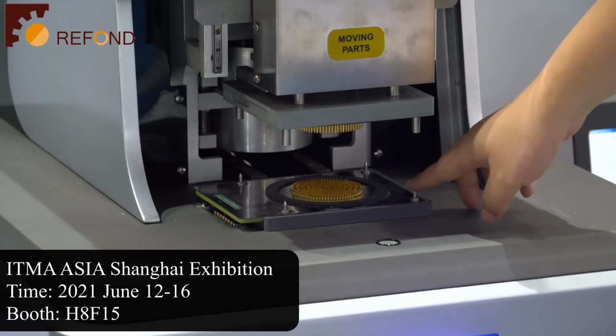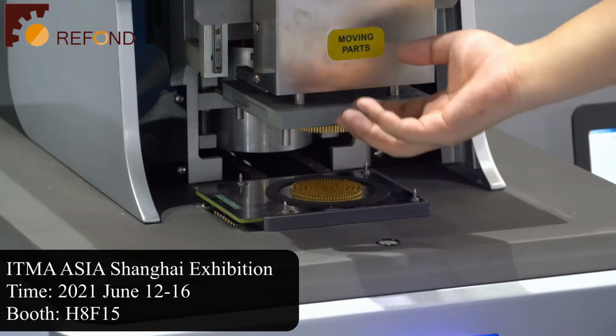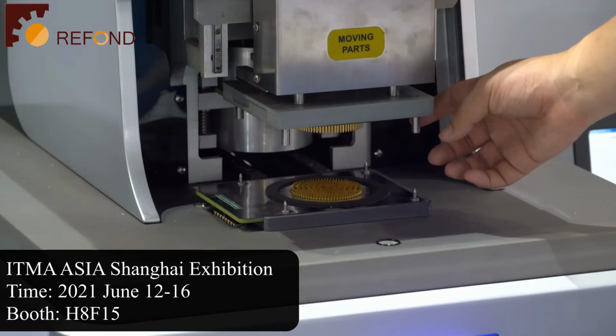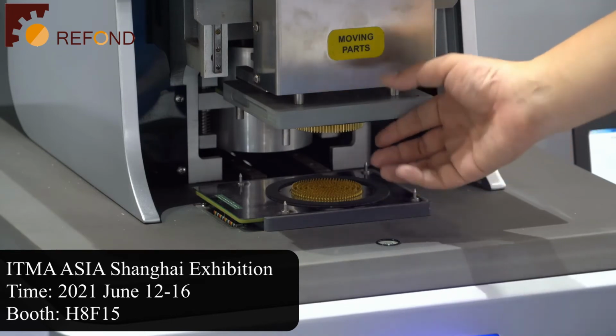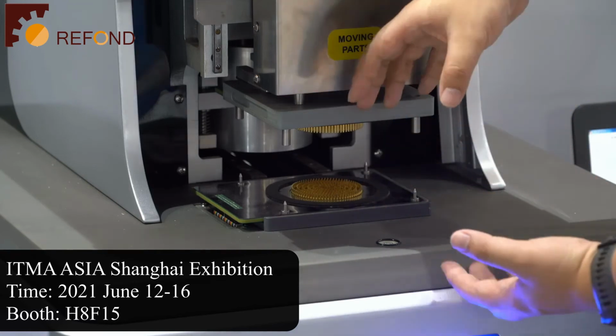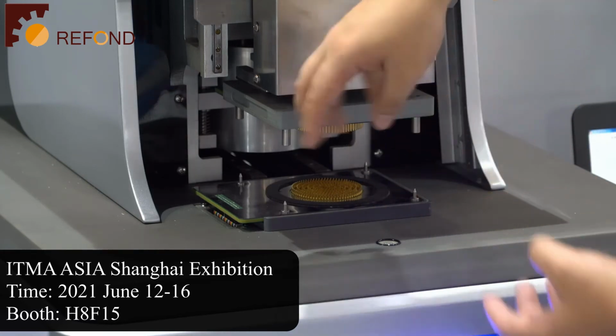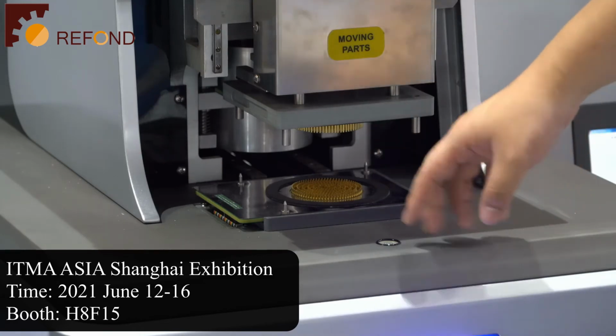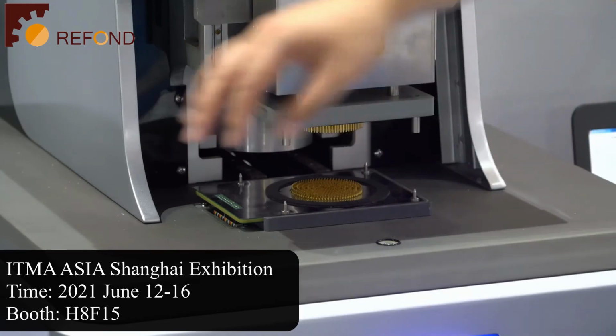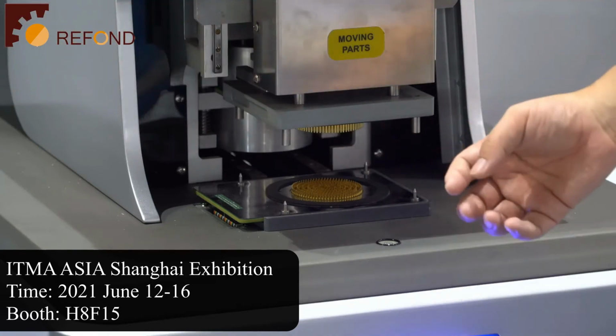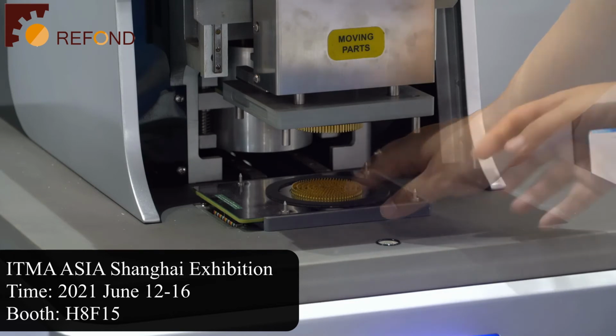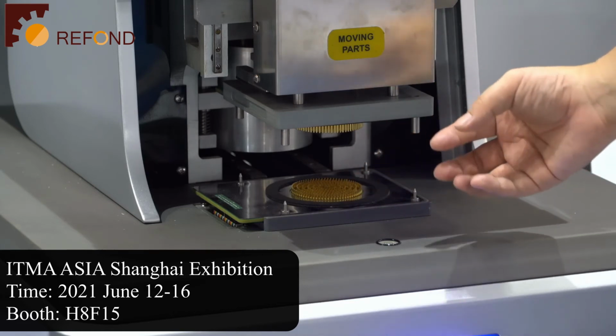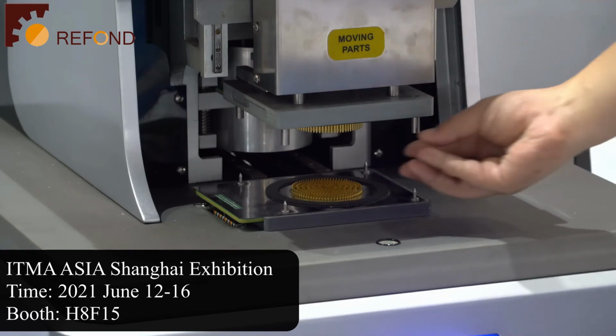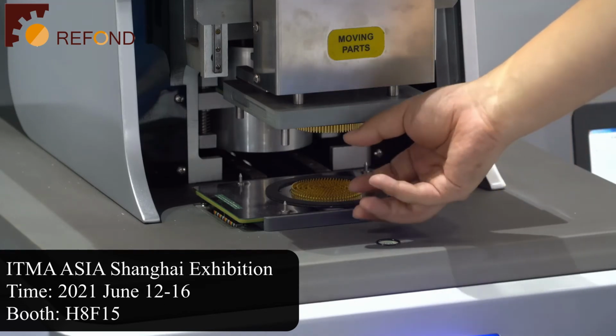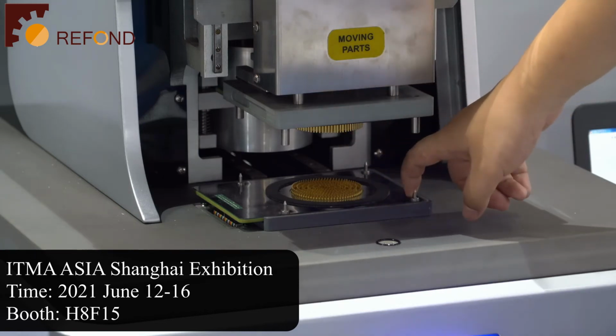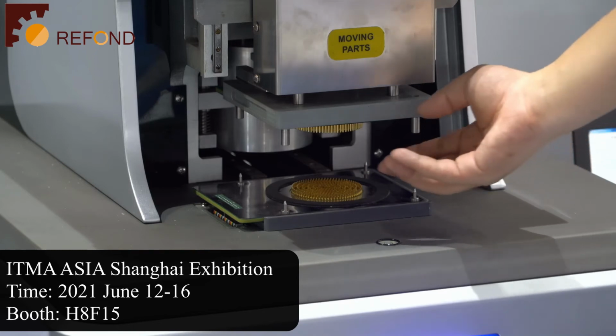When you use the cleaning function, the top test head will move up and then the cleaning cup will move forward and then be placed in between the top and bottom test heads. The top test head will come down and seal the inside of the cleaning cup. Then clean water will be pumped from outside to clean all the pipeline and also the testing probe. After the cleaning by the clean water, hot air will come into this test cup to dry the top and the bottom test probe to make sure that no excess water remains on the test probe.